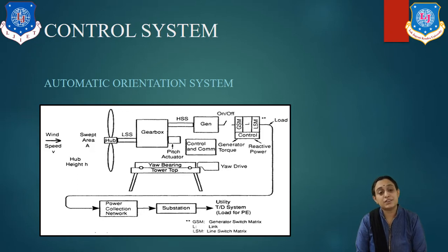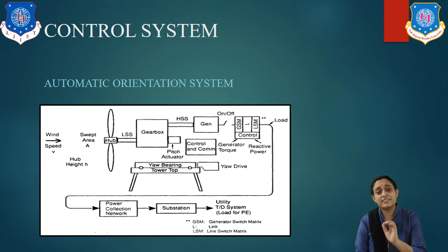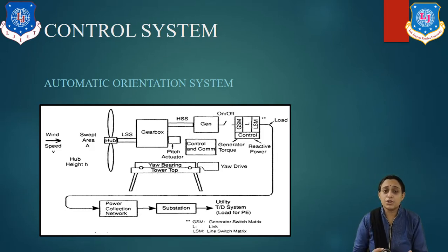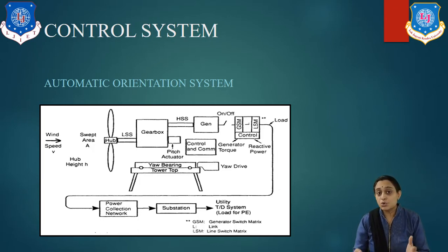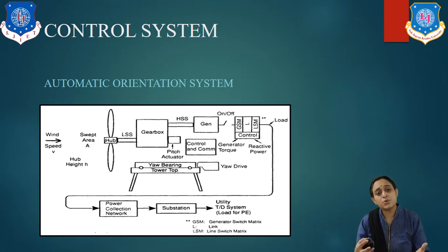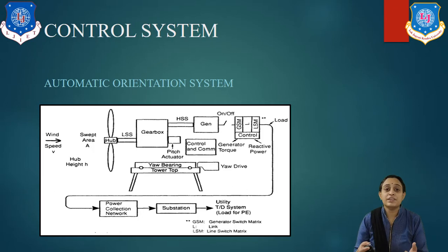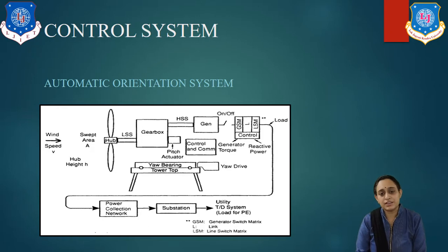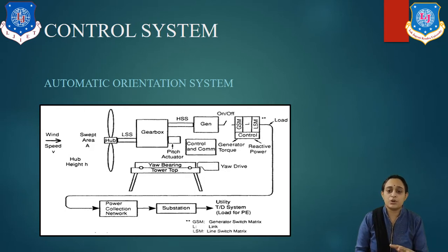The generator must rotate at constant speed because different speeds of rotation will create electrical output of variable frequency. The purpose of the controller is to control the effect of wind speed, wind direction, and shaft speed. The system is an automatic orientation system which keeps constant rotor revolution according to the wind direction and wind speed. If rotor revolutions increase or decrease beyond a certain limit, the generator must be stopped from generating power.